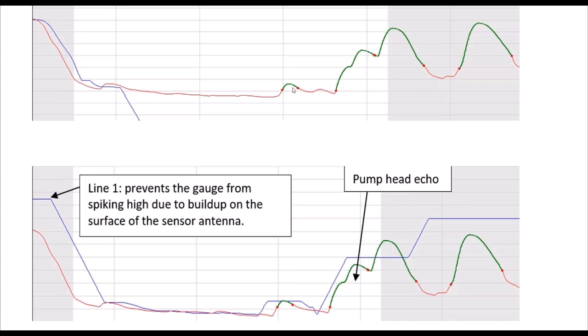So now here is an issue you can sometimes have when setting up these lift stations. Most of your newer lift stations now, they'll put them in subdivisions at the end of subdivisions, and they have to lock them to keep people out. So therefore it has a metal lid on the top. And so as soon as you close that metal lid, what can happen sometimes is it can create noise. Basically what's happening is that the signal is going down, bouncing off your water level, and then it's coming up and hitting that metal lid. And now what this does is produces multiple echoes. So let me go on to explain.